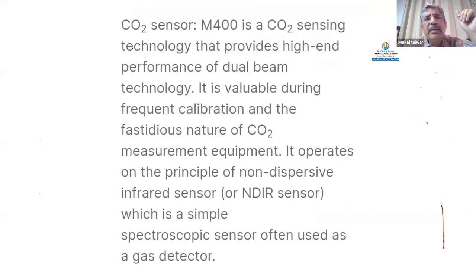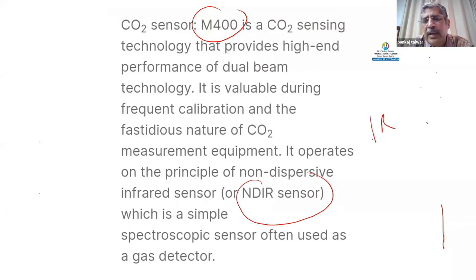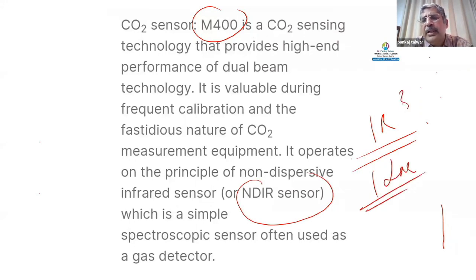Nowadays, we are moving towards CO2 sensors, something like M400 or NDIR sensors. They're called non-dispersive IR sensors. They are around 1 lakh expensive approximately, and they last for around 3 years. Then they go bad. So IR sensors are important for us. Buy an IR sensor. This is a basic infrared sensor. It works because CO2 gas absorbs at a wavelength of 4.3 micrometer. Let's remember this number. So they look at the absorbance of CO2 at a wavelength of 4.3 micrometer.